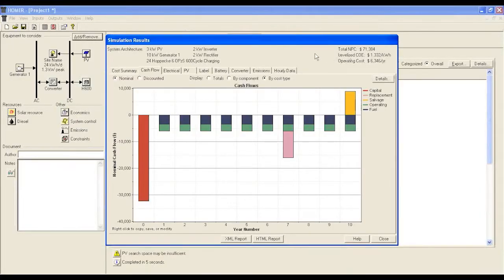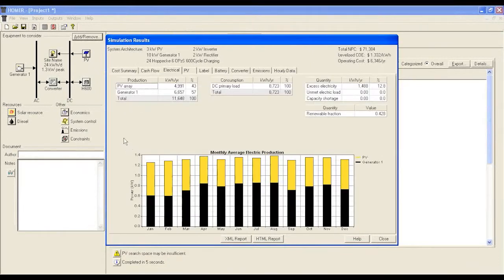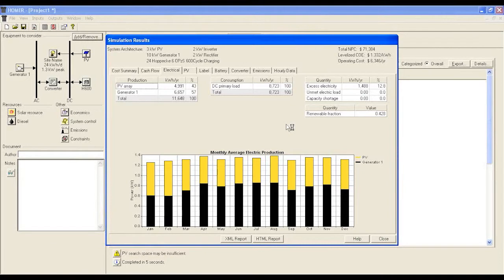The electrical tab gives you an idea of energy contribution from different power generation sources. Another important element in this tab is excess electricity. For any good solution dimension, the excess electricity should not be more than 5%, otherwise it will be considered an inefficient solution.